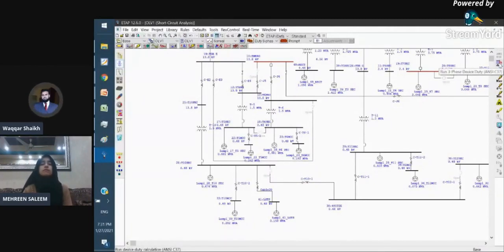In that case, you should run the other options. You can see run three-phase, line to ground, line to line, double line to ground. This option will give you all the symmetrical and asymmetrical faults, every type of fault, in the window. But if you are running the first option, it will give you only the symmetrical faults, the three-phase faults. There is another concept called asymmetrical fault analysis based on sequence components.